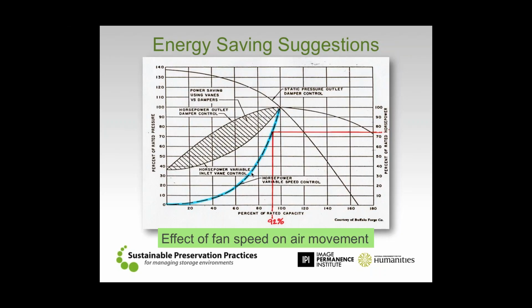So consider this as one possibility as you're thinking through and talking about whether we are being less efficient than we could. We oftentimes assume that just because a system was designed a particular way, that's the way it always has to run. What we tend to forget is that systems are designed for worst-case scenarios. They're designed to operate at these peak conditions in the summertime and in the wintertime. And in order to do that, they have to do the maximum amount of cooling or heating, but also send the maximum amount of air into the space in order to carry away the energy that's being imparted through the building and through the load.